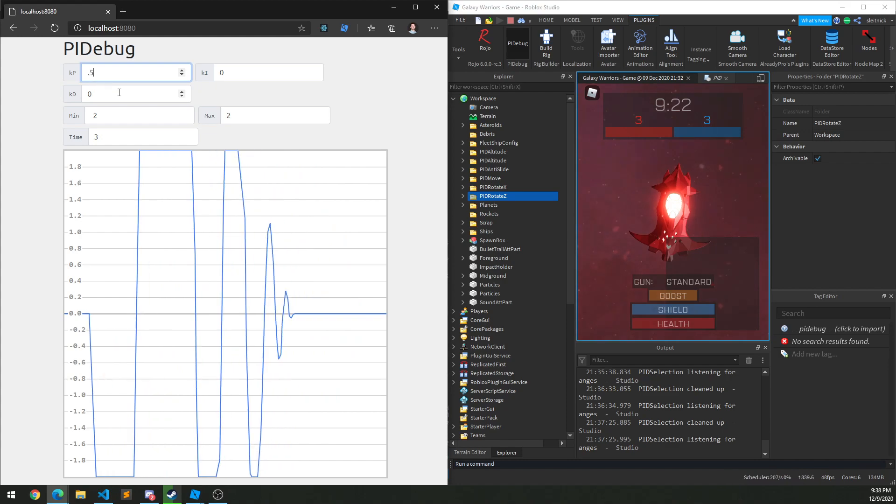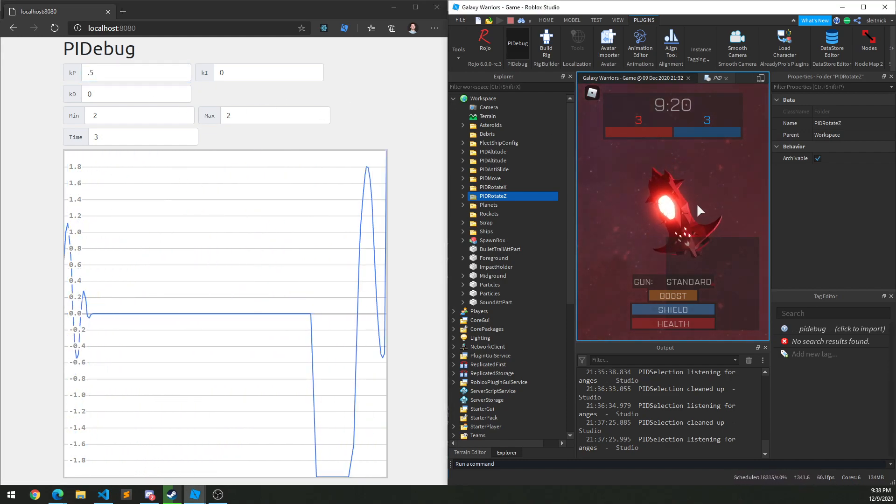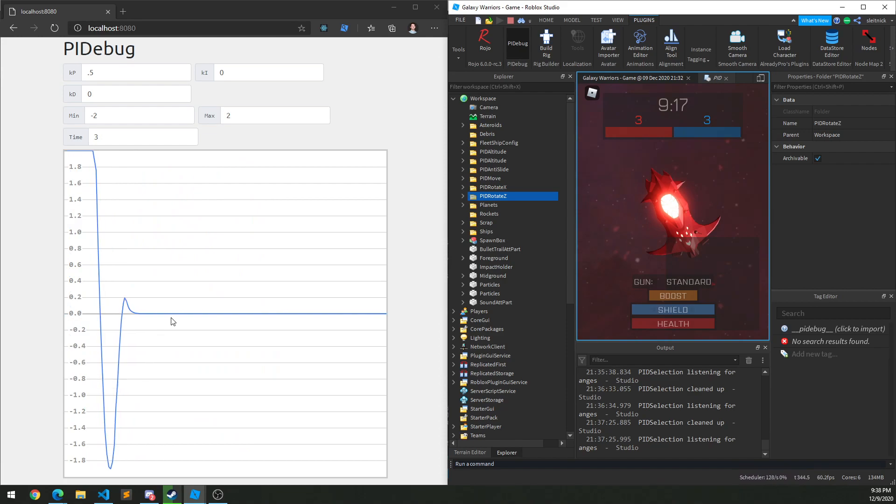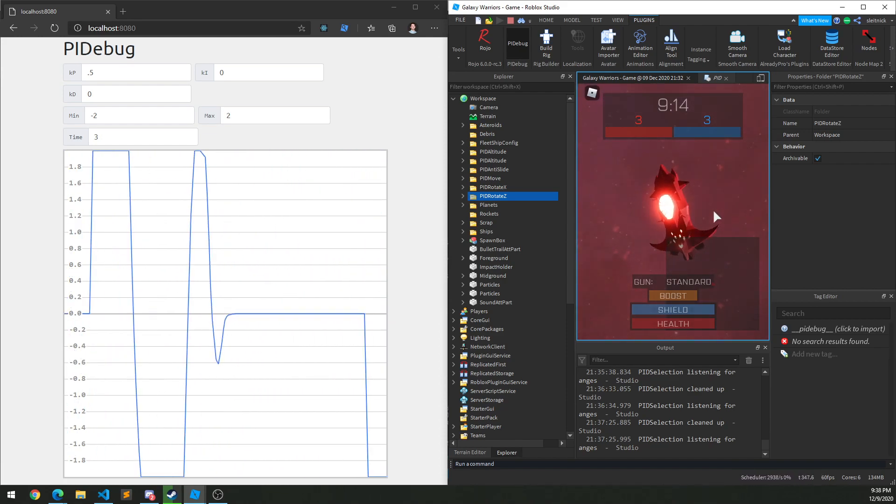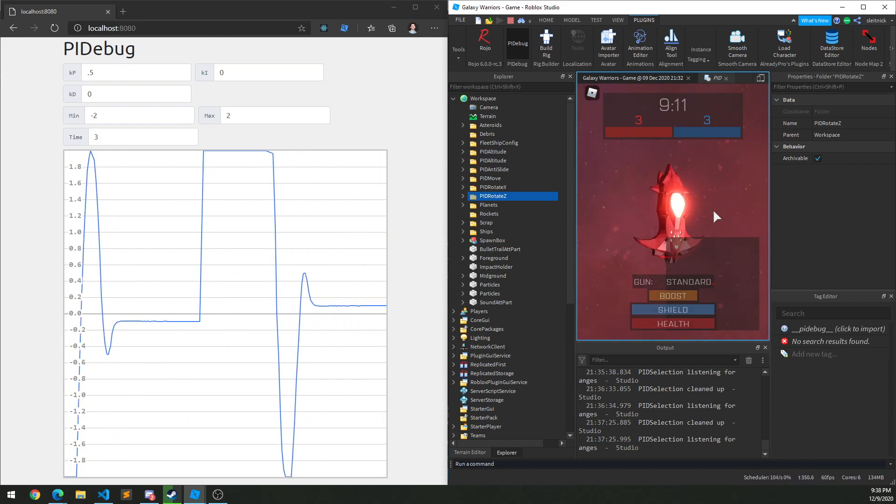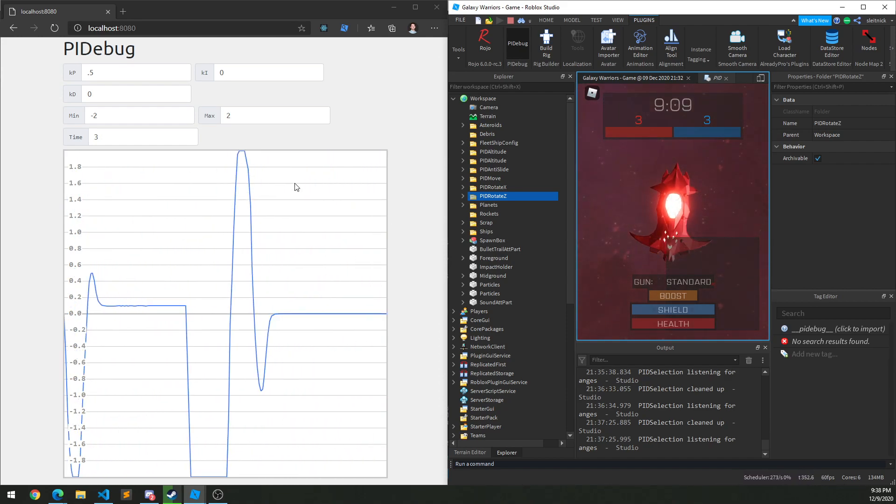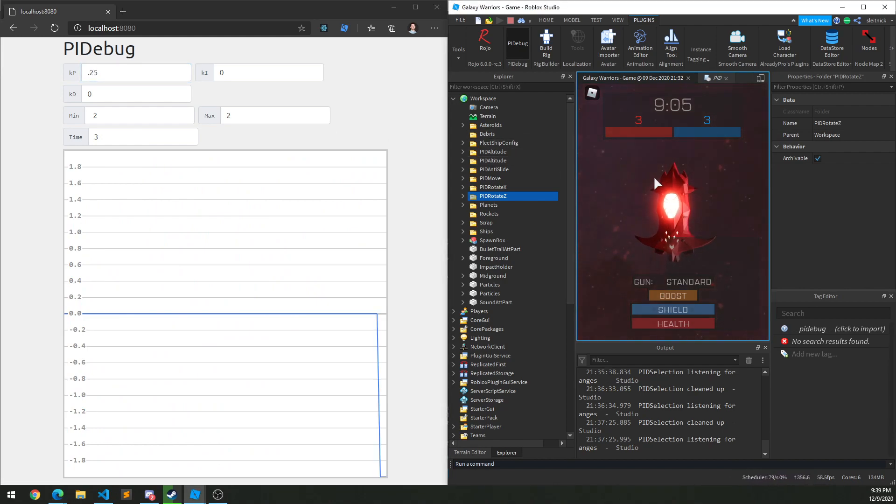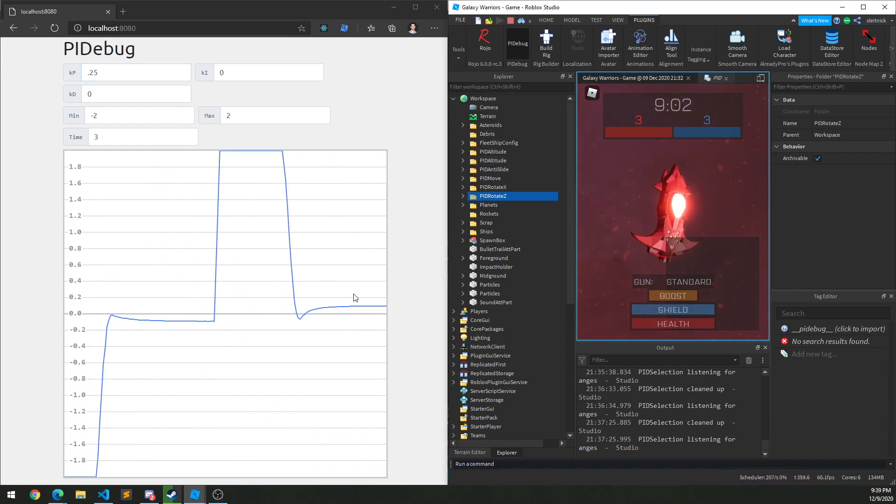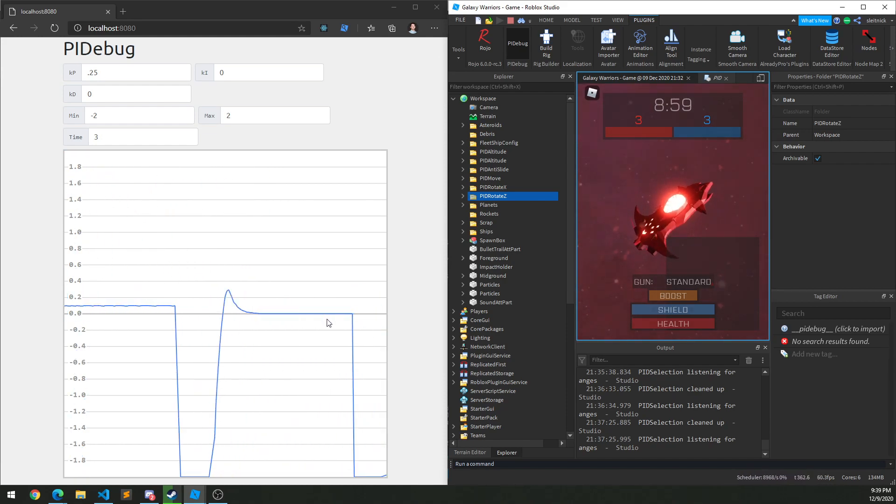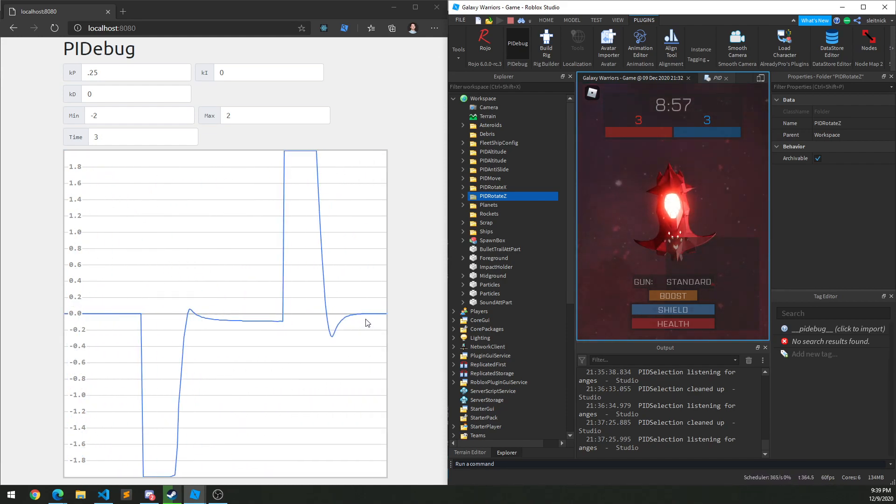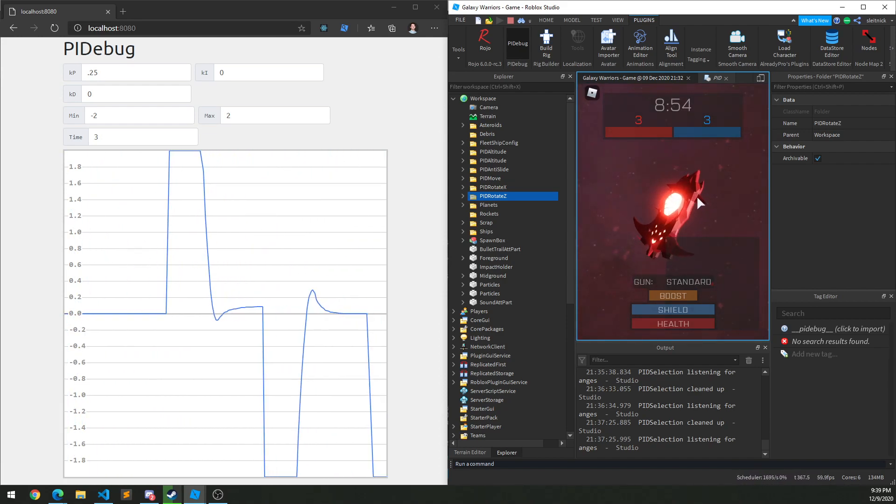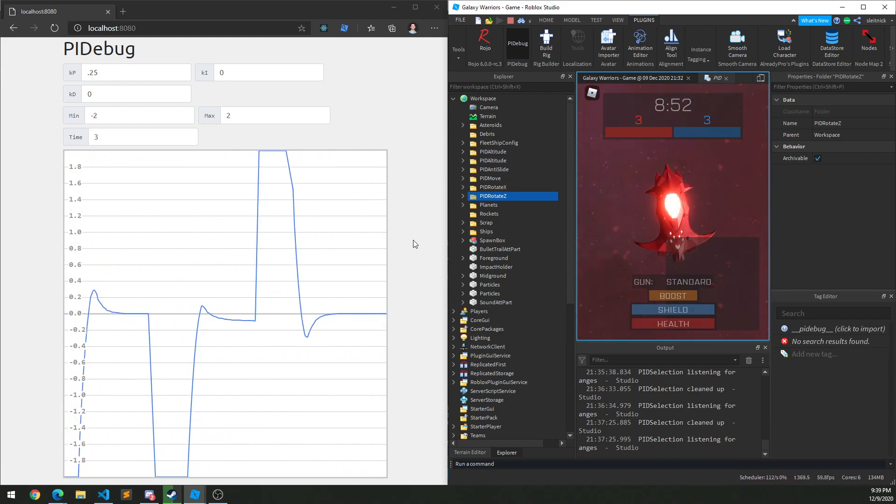So let's go in the other way. Maybe do 0.5. So now if I let go, you can see there's still a bit of oscillation back and forth when I turn. So it's still not quite good. I don't want it to bounce around like that. So if I try 0.25 maybe. And you can see that's a lot better. The curve seems to be getting to zero, but it still kind of overshoots a little bit.